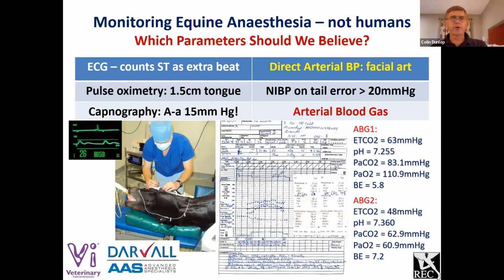I put this picture in here because it's a picture of a horse under anaesthesia using some of the same kind of equipment. And my comments are these. The ECG in horses generally gets the heart rate wrong because it counts the ST segment as a beat. The pulse oximeter is transmitting light through a tongue that's 1.5 centimeters thick. It always underestimates the real pulse oximetry oxygen value by about 5%. And during an anaesthetic, it can drop to a point that it's non-functional, reads 80 in a horse that's clearly not hypoxic. The capnograph has a 15 millimeter of mercury AA gradient, so it's a glorified respiratory rate counter. Unless you've got a blood gas, you can't believe the information from the capnograph.